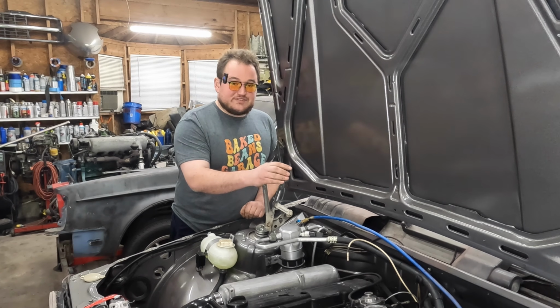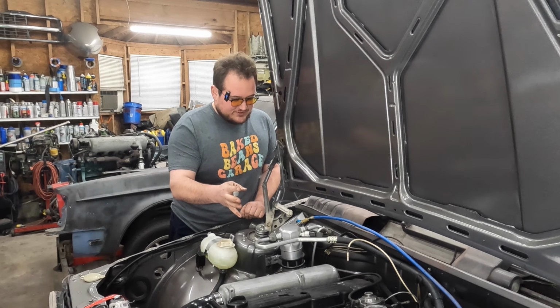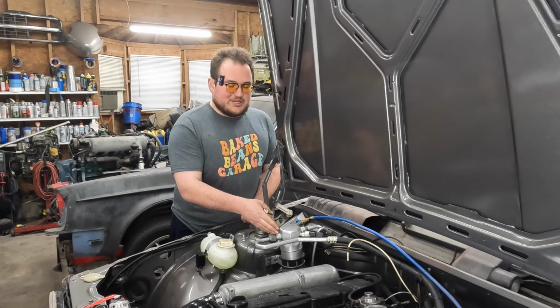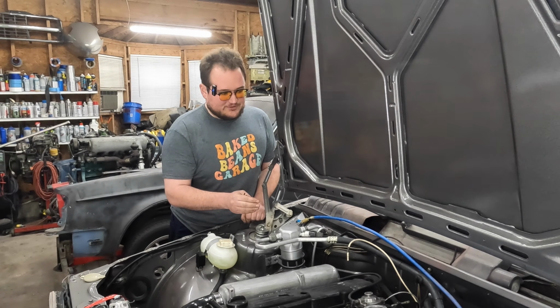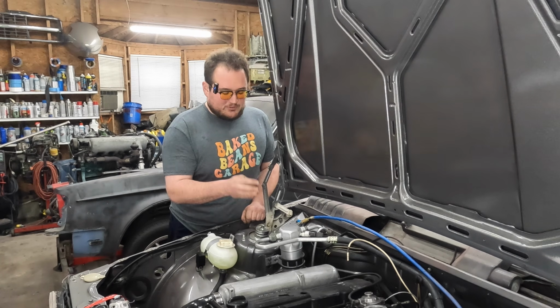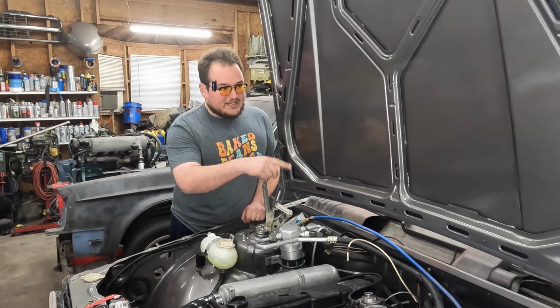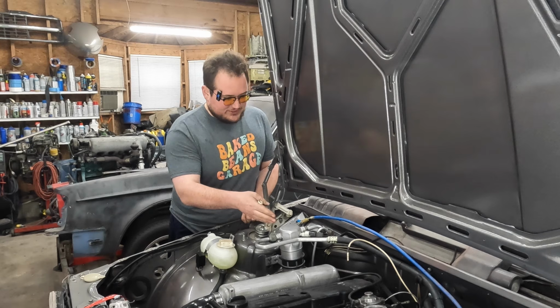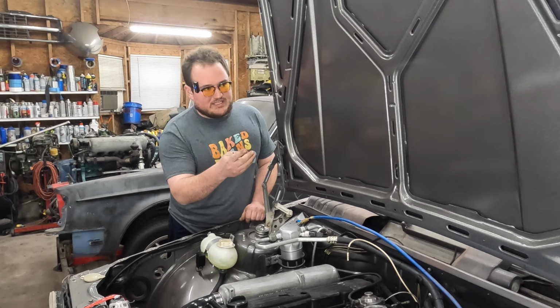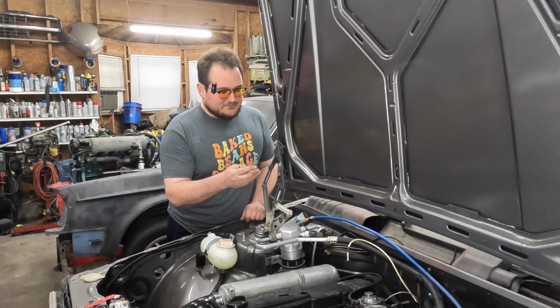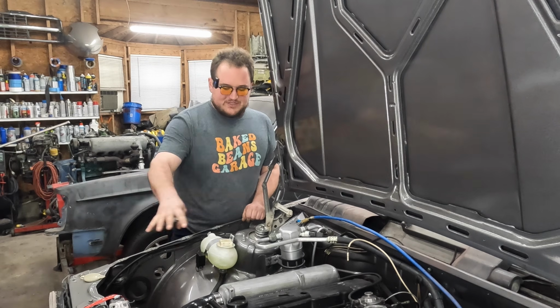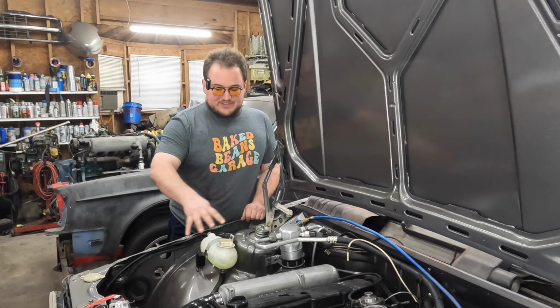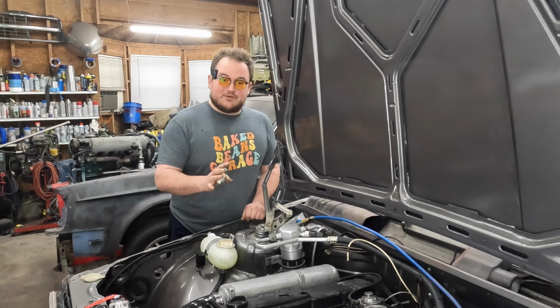That being said, I think this condenser is doing its job just fine. With that new information, I don't think I'm going to need a high pressure cutout switch. It's still a little chilly, but once we get a nice hot and humid day, I can set the manifold gauge back up and really stress test this system and see if I get anywhere near the dangerous area. Also, since we have a mechanical fan, there's never going to be a situation where there isn't wind across that condenser, so I think I'm good.